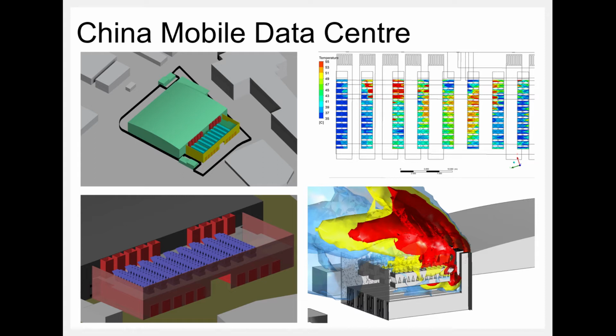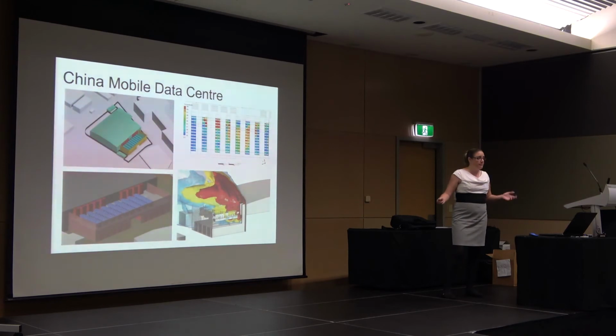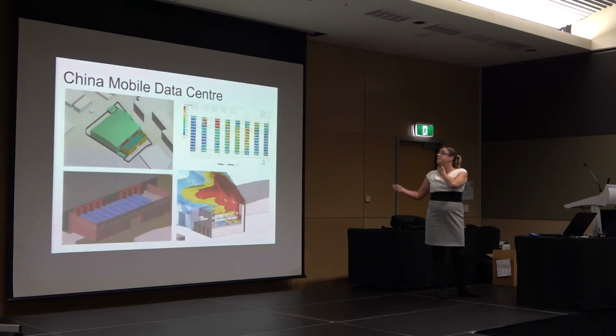So we were looking at things like changing the grate porosity that these condensers were sat on, putting physical solid barriers at the ends of the condensers. We probably tried 3 or 4 different options and got to something that was workable, but where you could still easily maintain these bits of kit. There wasn't the option to actually move any of these things. We were a bit late for that.